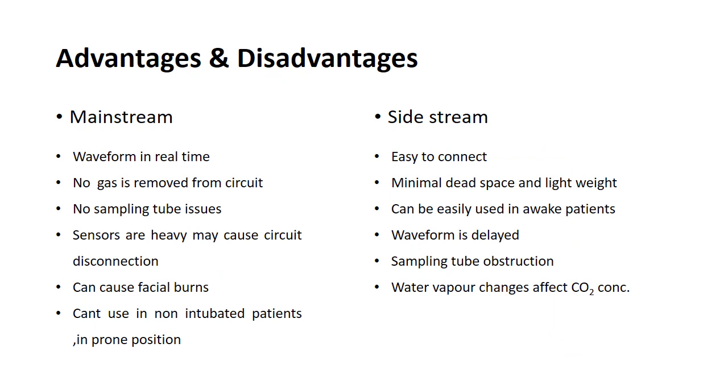So now coming to the advantages and disadvantages of these mainstream and sidestream analyzers. Mainstream analyzer waveform comes in real time. No gas is removed from the circuit. No sampling tube issues. Sensors are heavy and may cause circuit disconnection. It can cause facial burns. It cannot be used in a non-intubated patient or in the prone position.